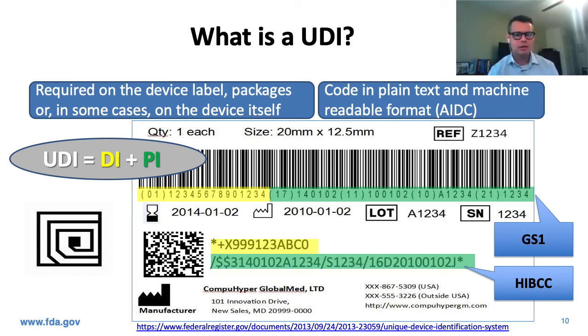As shown here, UDI is a unique numeric or alphanumeric code that generally consists of the device identifier, a mandatory fixed portion of UDI that identifies a labeler and specific version or model of the device, and the production identifier, a conditional variable portion of the UDI, which can identify lot or batch number, serial number, expiration date, date of manufacture, and distinct identification codes.